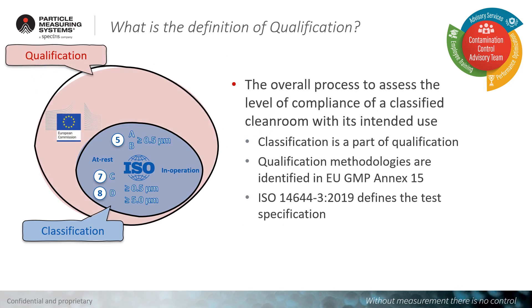Talking about qualification — what is the right definition? The draft clarifies that it is the overall process to assess the level of compliance of a classified cleanroom with its intended use. Using simple words, classification and qualification are not the same thing. Qualification is a wider process that contains classification inside it. Like all qualification processes, it must comply with all the formal requirements of Annex 15, and all verifications required must comply with the testing methodologies indicated in ISO 14644 Part 3, published last year.